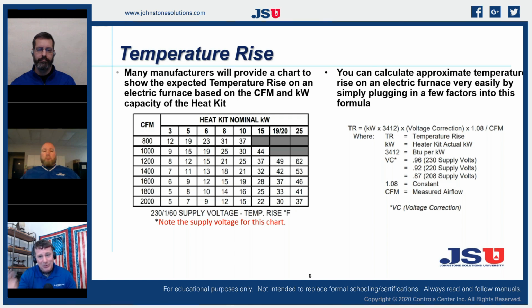We could go back to using our meter and verifying all of our kW and our BTUs. And if we know the power factor and the actual voltage going through our motor, we can calculate that out. So we could even set our CFM based on our temperature rise, not by temperature probes, but by watts and BTUs. So that's when we get into this other calculation. We've already figured out our CFMs. We can now do our kW times 3412, which is getting BTUs, times our voltage correction, times that 1.08 factor, divided by our CFM, and voila, we have a calculated temperature rise for our piece of equipment.